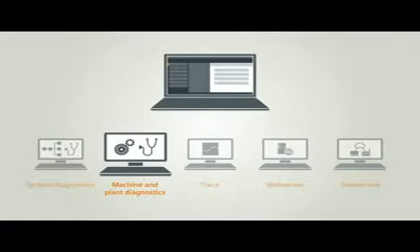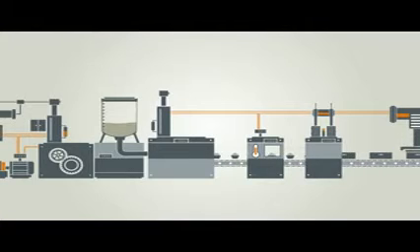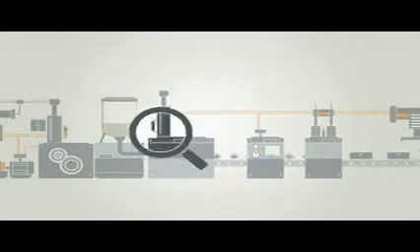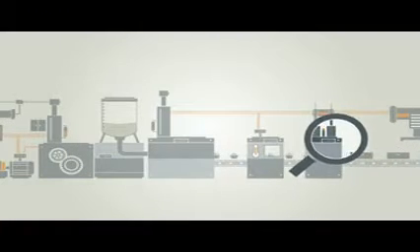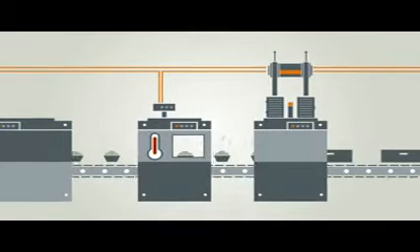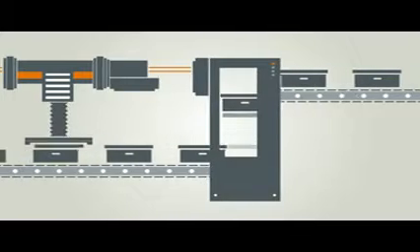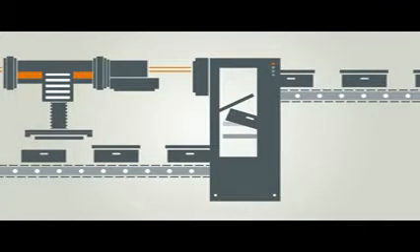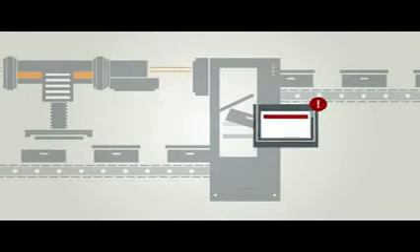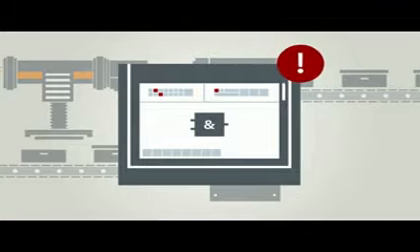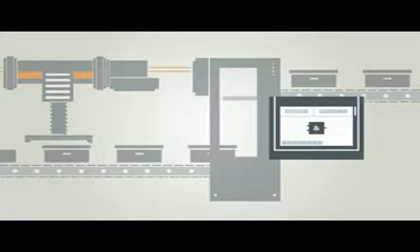With the process diagnostics ProDiag integrated in the TIA portal, you can individually configure the monitoring of process variables for your plant and thus troubleshoot faults while the system is running. For example, if a temperature is exceeded, or if a lifting unit no longer reaches its limit position, you can perform the diagnostics directly on the operating device with preset objects for this purpose. As a result, all faults can be detected and remedied even without a programming device.